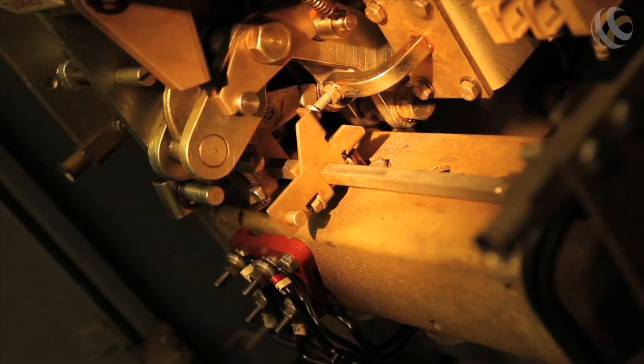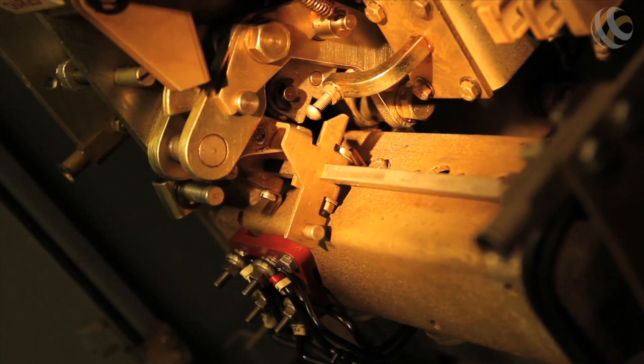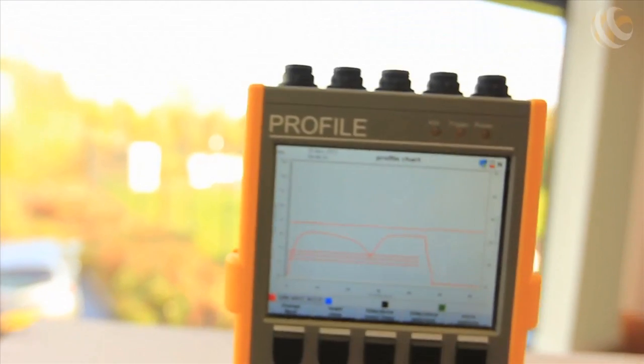As a consequence, a technique called trip coil profiling was developed as a condition monitoring technique to allow the user to test the breaker while energized, thereby capturing that vital first trip. This very simple and efficient test helps to easily pinpoint any potential problems within either the trip coil or circuit breaker main operating mechanism.